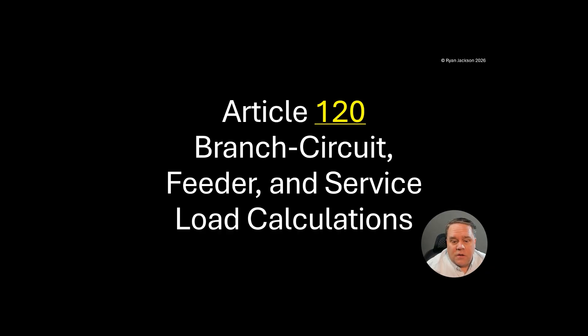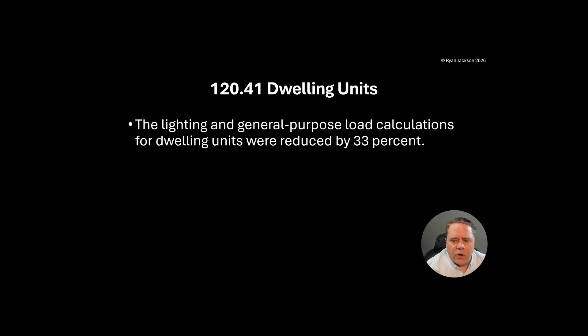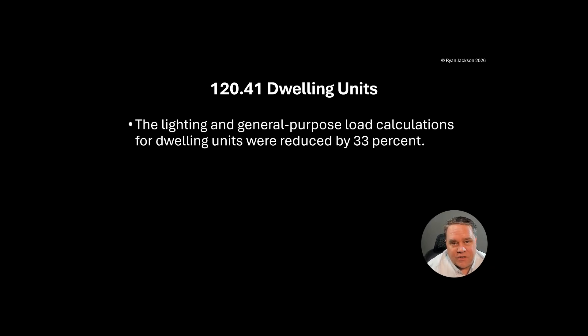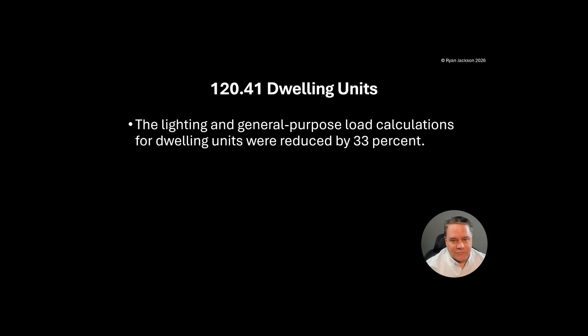Article 120 covers branch circuit, feeder, and service load calculations. We're going to go in reverse order — we'll talk about 120.13, but we've got to talk about 120.41 first. Otherwise the change to 120.13 is not going to make any sense. So here's the deal: the lighting and general purpose load calculations for dwelling units were reduced by 33%.